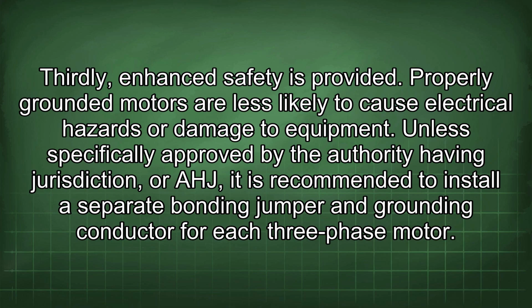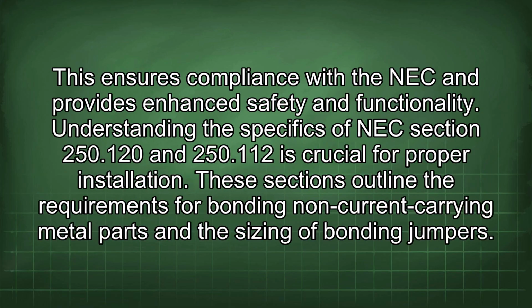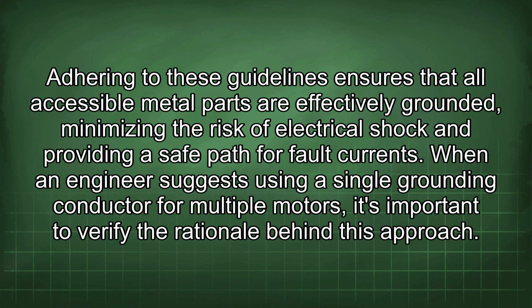Unless specifically approved by the authority having jurisdiction, or AHJ, it is recommended to install a separate bonding jumper and grounding conductor for each three-phase motor. This ensures compliance with the NEC and provides enhanced safety and functionality. Understanding the specifics of NEC Section 250.120 and 250.112 is crucial for proper installation. These sections outline the requirements for bonding non-current carrying metal parts and the sizing of bonding jumpers. Adhering to these guidelines ensures that all accessible metal parts are effectively grounded, minimizing the risk of electrical shock and providing a safe path for fault currents.